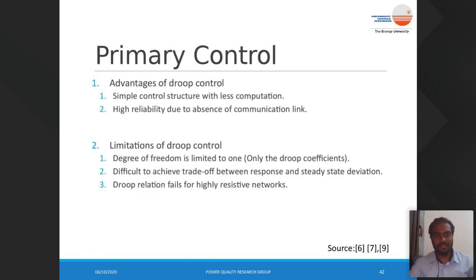So the advantages of this decentralized control, or simple control structure, is that it's only one gain which is going to decide whether the source has to increase its power output or decrease its power output based on the frequency of the grid, and it is highly reliable due to the absence of a communication link.